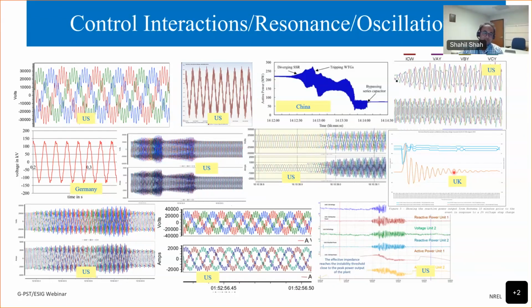And although all these oscillations look quite different, one thing common for the oscillations that you are seeing here is that I call them local interactions. So although these oscillations can be experienced at a bigger part of the system, for these local interactions we can always divide the network into two parts where, if we dig down enough, we can show that these are really oscillations between one part of the system against another part. For example, in this ERCOT case, the type 3 wind power plant is oscillating against a series compensated transmission line, whereas in this case in Germany, the offshore wind power plant is oscillating against an HVDC converter.